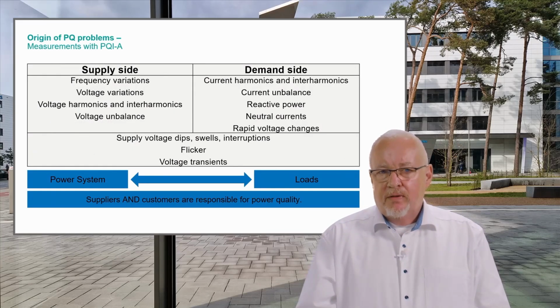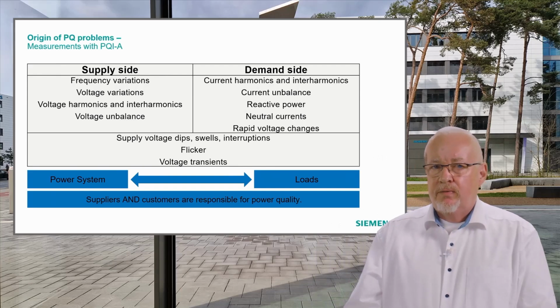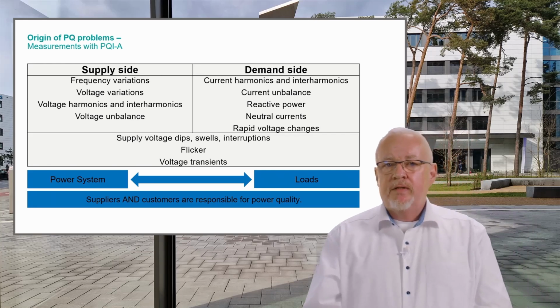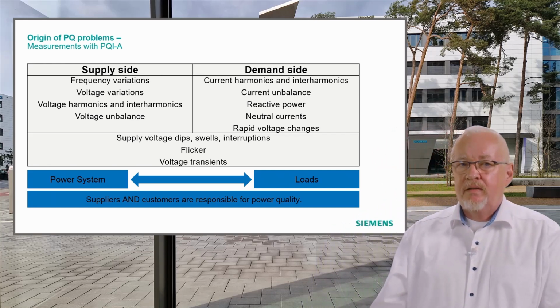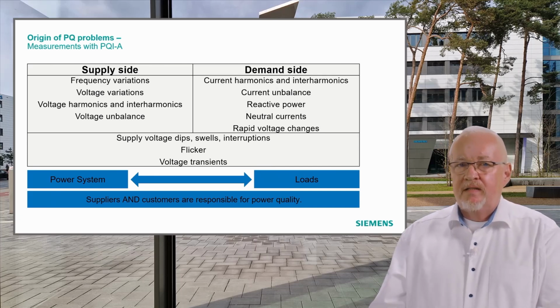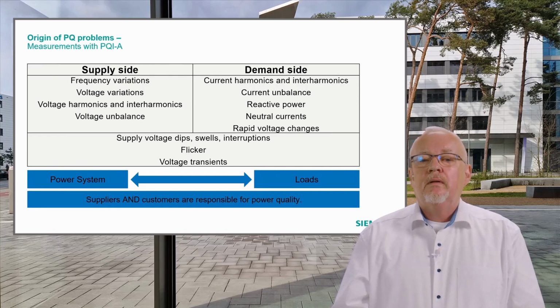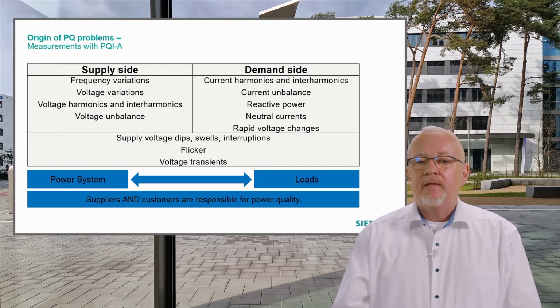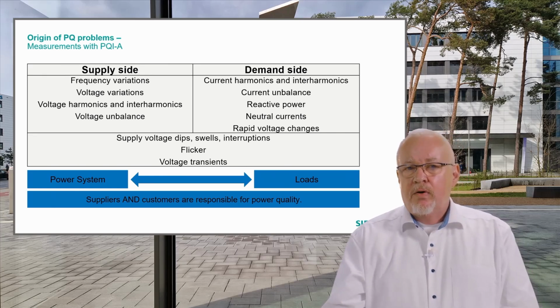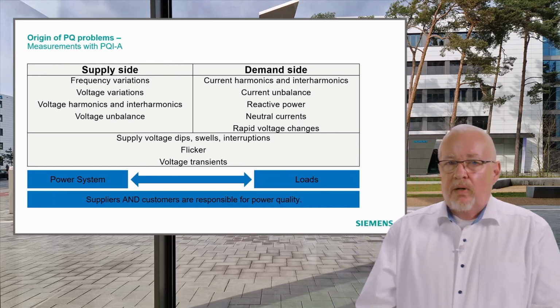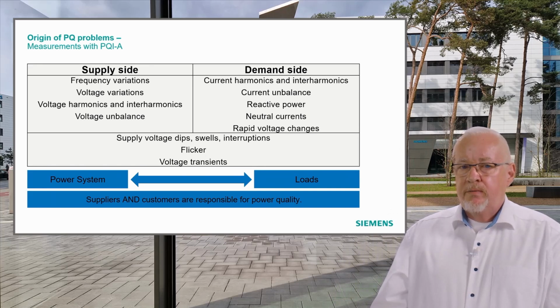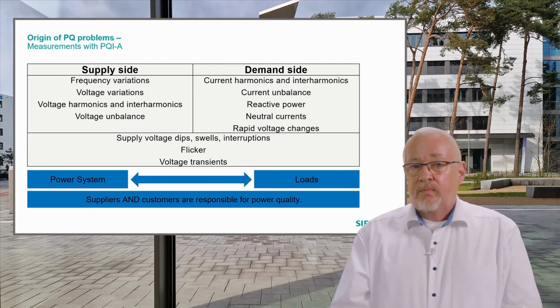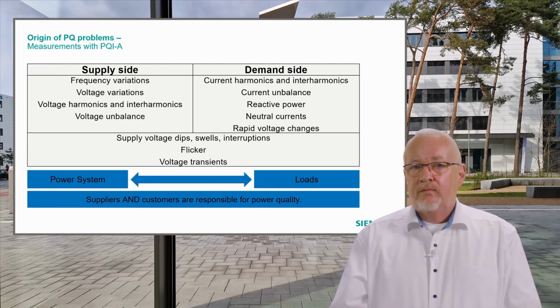The origins of power quality problems. Who is responsible for power quality disturbances? We have the supply side, which is responsible for frequency variations, voltage variations, voltage interharmonics and harmonics, and voltage unbalance. The demand side is mainly responsible for current harmonics and interharmonics, current unbalance, reactive power, neutral currents, and rapid voltage changes. Both sides are responsible for power quality problems like supply voltage dips, swells or interruptions, flicker, and voltage transients. So supply and demand side are responsible for good power quality.